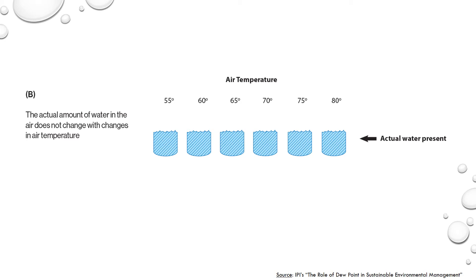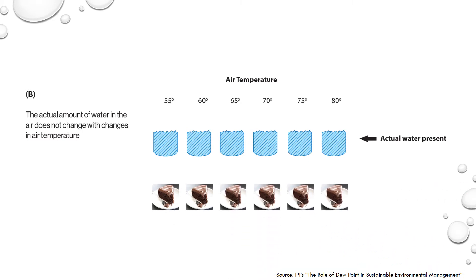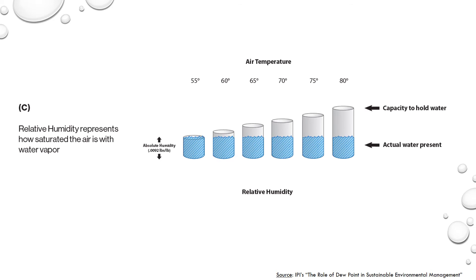Just like how the bodybuilder and the little girl ate the same amount of cake, the volume of water in the air is the same for each temperature — just changing the temperature alone does not change how much water is present in the air. When the two diagrams are combined, we can visualize how that same volume of water fills each of the different cylinders. Just like how the little girl was 90% full from that same amount of cake, the air at 55 degrees is full — it is at capacity. When the air is warmed to 60 degrees, there's a little bit more room left at the top of the cylinder. It has a slightly higher capacity to hold water. The air is 84% saturated with water, or we could say that the relative humidity at 60 degrees is 84%.